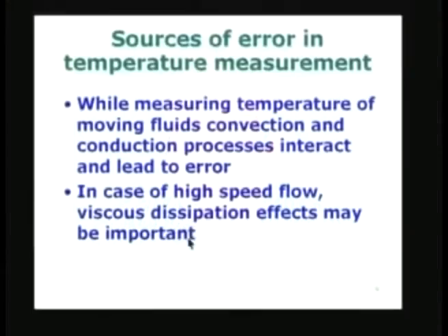The fluid will actually heat up very close to the probe, because the probe is in a region where the boundary layer is going to be present right next to the probe, and the high speed flow is going to decelerate next to the surface, and because of large velocity gradients which are present near the probe surface, there may be a significant amount of heating. So, in high speed applications, this may be a very important error which has to be taken into account.